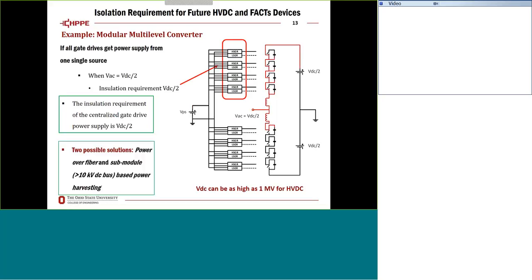Then if we look at the case when all the upper modules are connected in series, marked in red in the circuit, you'd see that all the gate drives need to sustain half of VDC. This means you need 500 kV isolation on the gate drive board. Thinking about a 500 kV isolation transformer, that is huge, and it's extremely difficult to manage on a piece of PCB board for a gate drive, which is very low voltage. So for HVDC and similar applications, these approaches are not applicable anymore.